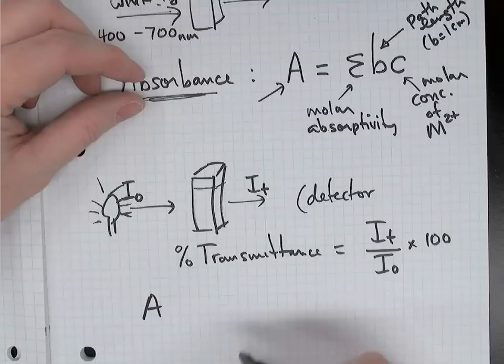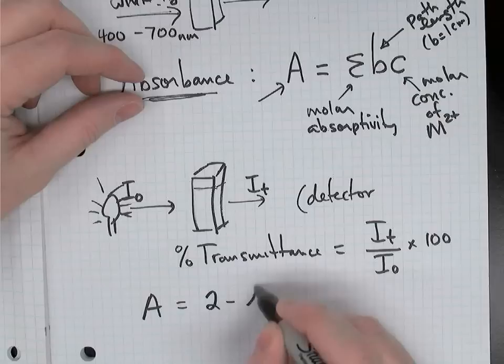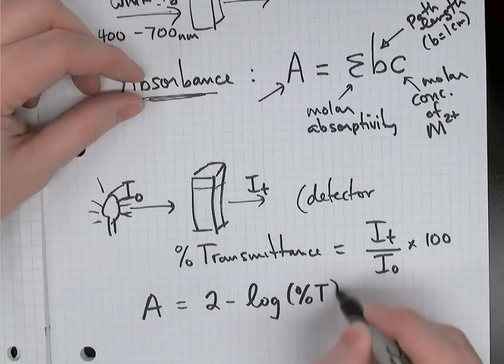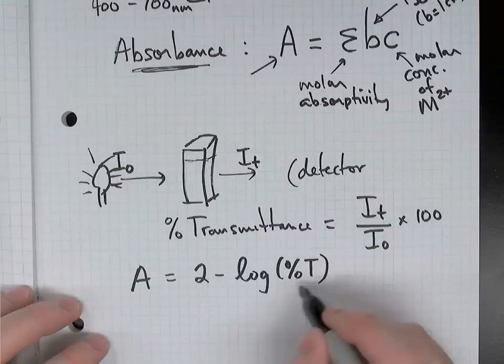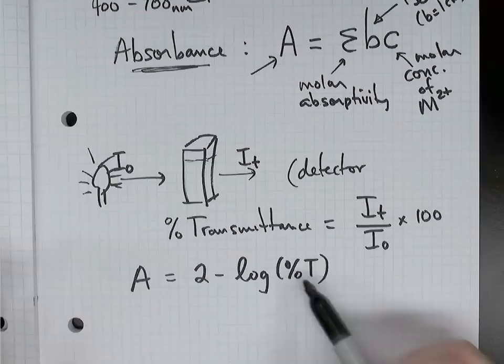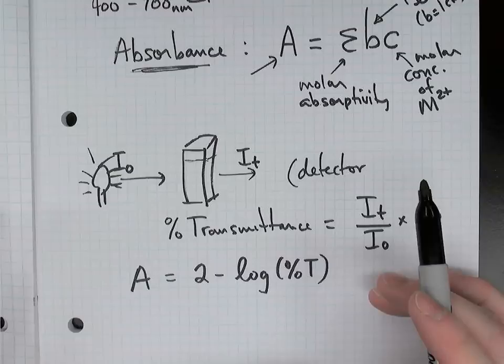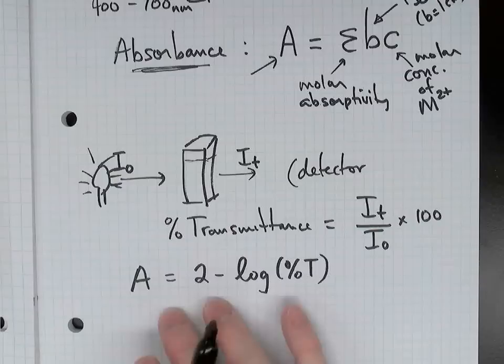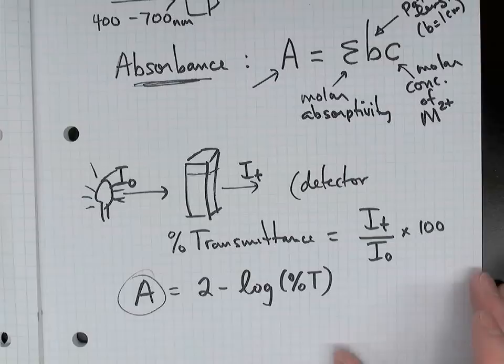Absorbance can be calculated from transmittance using the formula: 2 minus the base-10 logarithm of percent transmittance. For example, if percent transmittance is 100%, the log of 100 is 2, so 2 minus 2 gives zero absorbance. When there's 100% transmittance, there's zero absorbance. Some older spectrophotometers measure transmittance; some newer ones measure absorbance automatically.